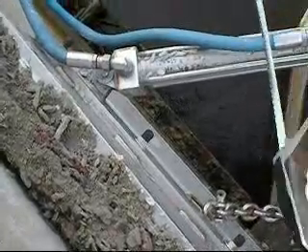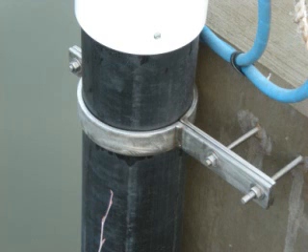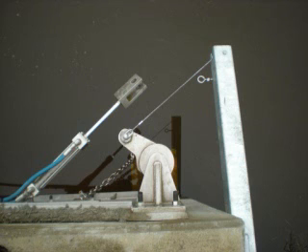It would be no problem to open the control cabinet and tamper with or destroy hundreds of dollars worth of hydraulic components. A clever miscreant could also figure out a way to jam the float in the float well of the GH850. This would cause the hydraulic cylinder to hold the gate open regardless of the water level. The Golden Harvest control mechanism could be vandalized in ways that make a huge mess or cause potential flooding, take days or weeks to repair, and cost thousands of dollars.